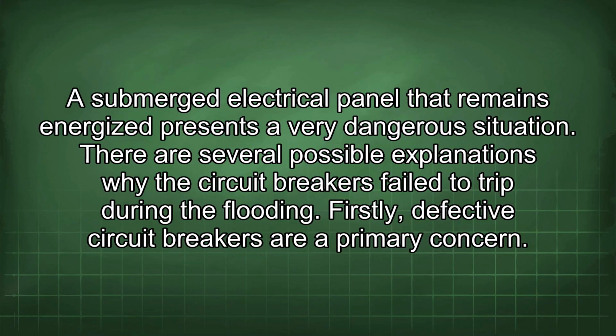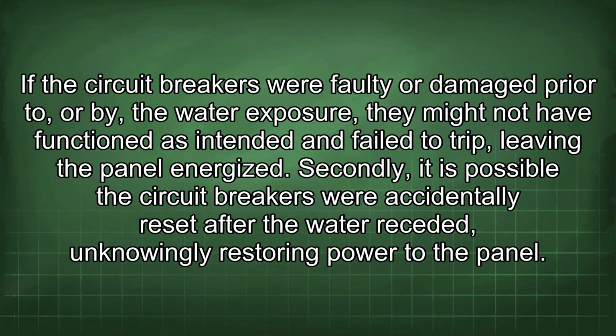A submerged electrical panel that remains energized presents a very dangerous situation. There are several possible explanations why the circuit breakers fail to trip during the flooding. Firstly, defective circuit breakers are a primary concern. If the circuit breakers were faulty or damaged prior to, or by, the water exposure, they might not have functioned as intended and failed to trip, leaving the panel energized.